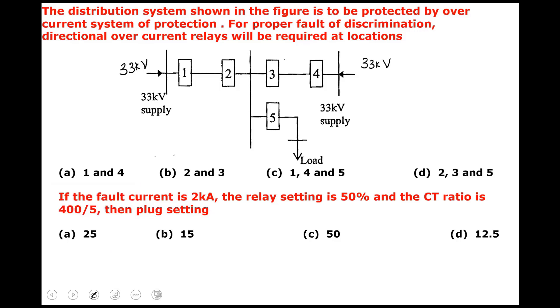To decide which relays need to be directional, first identify the zone of relay 1 and 2. This is the zone of relay 1 and 2. You exactly simulate the fault in the middle of the zone, and see how the fault currents will flow. Before that, you have to determine the normal current directions.